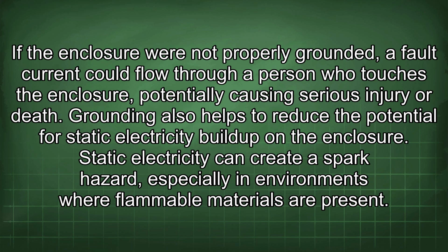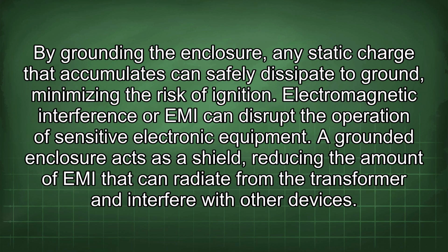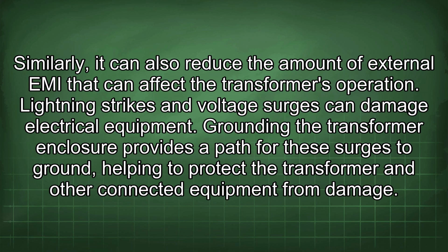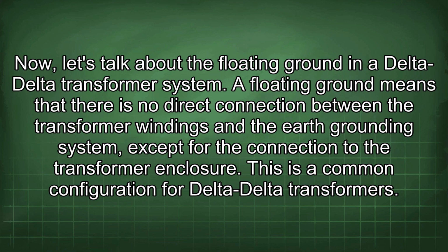Grounding also helps to reduce the potential for static electricity buildup on the enclosure. Static electricity can create a spark hazard, especially in environments where flammable materials are present. By grounding the enclosure, any static charge that accumulates can safely dissipate to ground, minimizing the risk of ignition. Electromagnetic interference, or EMI, can disrupt the operation of sensitive electronic equipment. A grounded enclosure acts as a shield, reducing the amount of EMI that can radiate from the transformer and interfere with other devices. Similarly, it can also reduce the amount of external EMI that can affect the transformer's operation. Lightning strikes and voltage surges can damage electrical equipment. Grounding the transformer enclosure provides a path for these surges to ground, helping to protect the transformer and other connected equipment from damage. Now let's talk about the floating ground in a delta-delta transformer system.